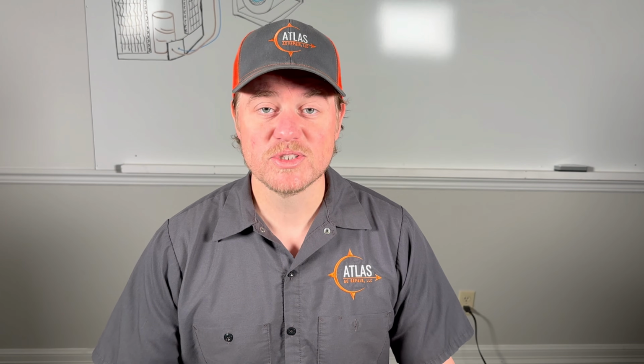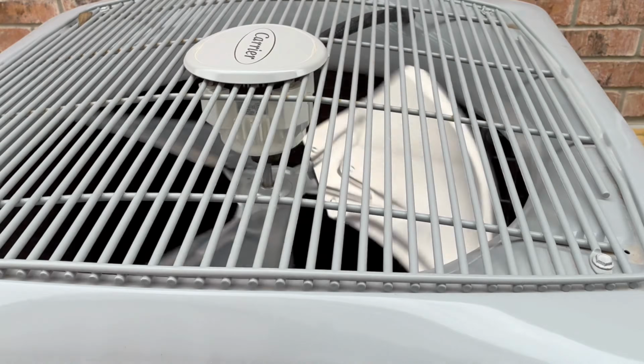That being said, what we saw, the primary type of heat that comes from a heat pump uses just the outdoor unit to heat your home. And then when temperatures drop below 40 degrees and the unit starts accumulating ice, it uses defrost mode in the heat kits for a short period of time to dethaw the unit, and sometimes we see a lot of steam that comes off of it.